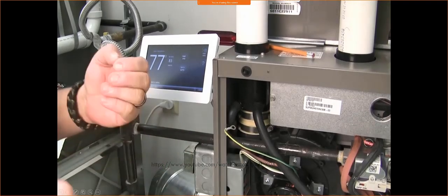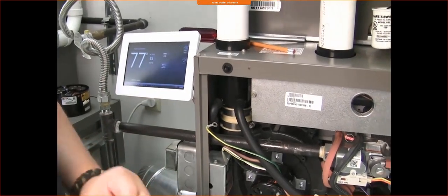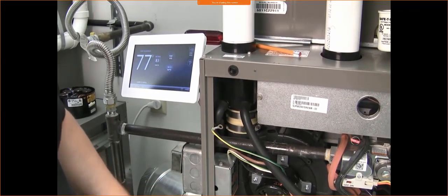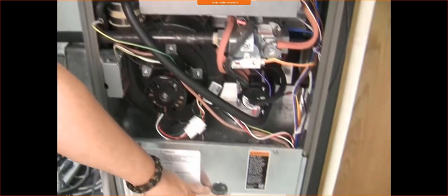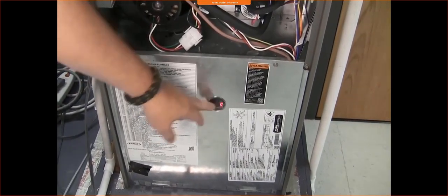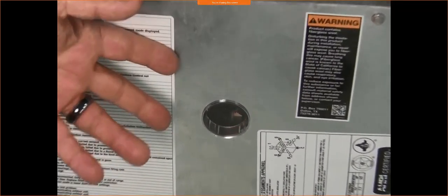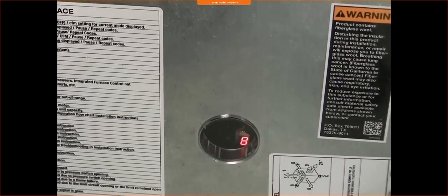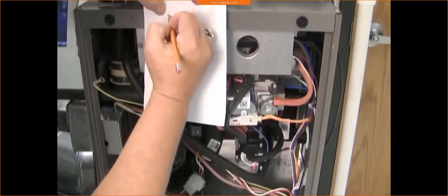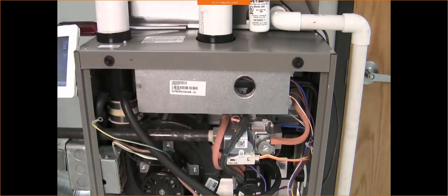Today we're going to talk about how to read error codes on a furnace. We're going to start off with reading the error code while power is still applied to the furnace, and to do that we're going to look through the visual inspection down here to the flashing 7-segment display, which is going to give us error codes. It's going to start with an E and then 3 numbers following to tell us what the code is. So in this case, we have an E250. So I would simply write down E250 to record that, and then I would go down here to the chart to E250, which tells me I have an open limit switch. At this point, then I would troubleshoot my limit switch.